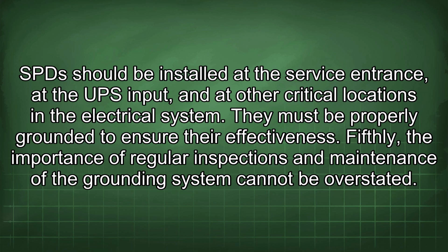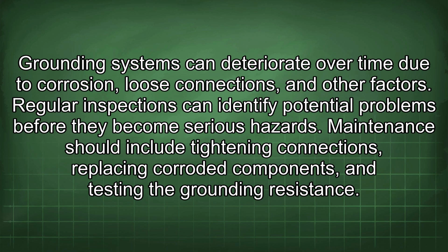Fifthly, the importance of regular inspections and maintenance of the grounding system cannot be overstated. Grounding systems can deteriorate over time due to corrosion, loose connections, and other factors. Regular inspections can identify potential problems before they become serious hazards. Maintenance should include tightening connections, replacing corroded components, and testing the grounding resistance.